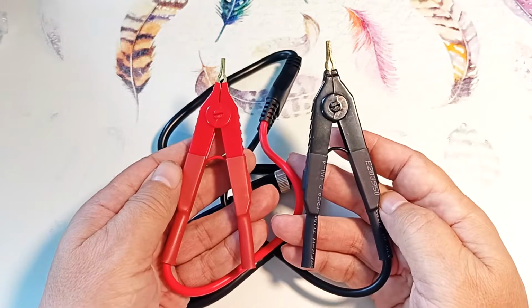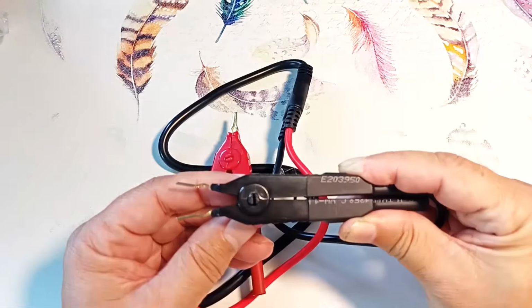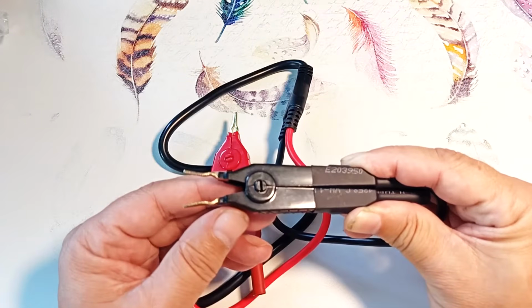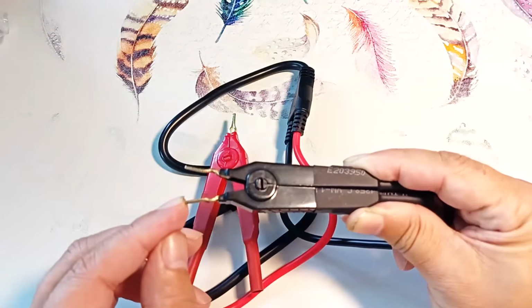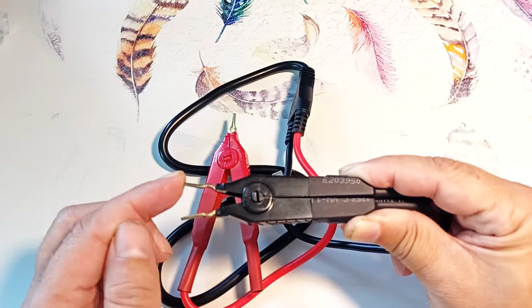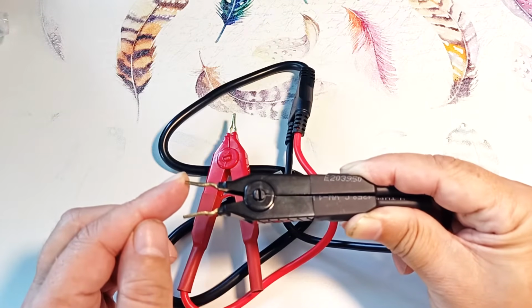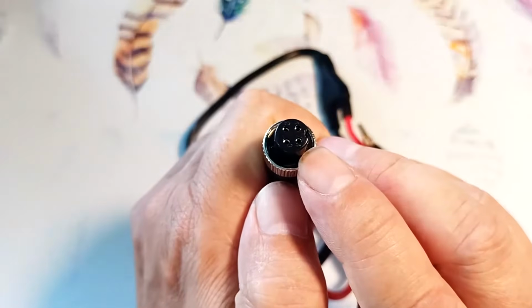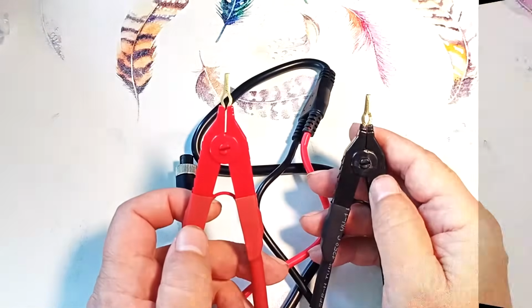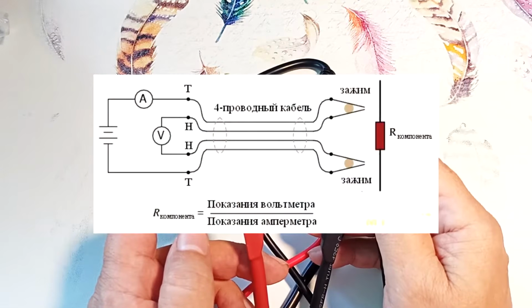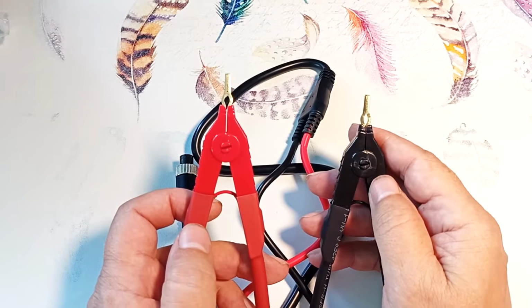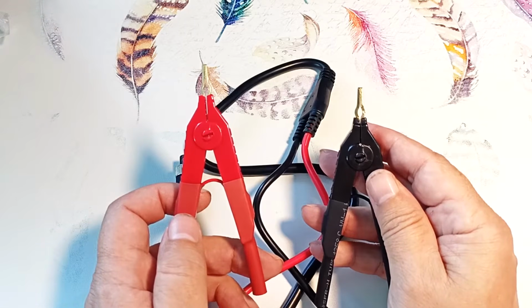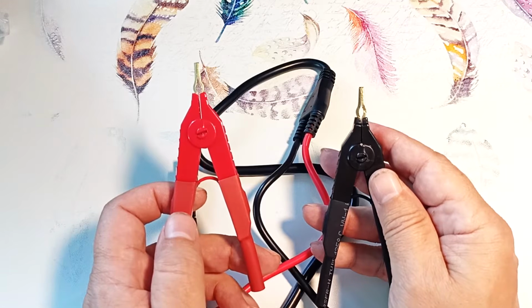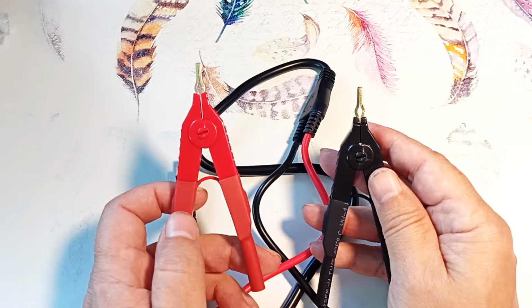Kelvin probes deserve a more detailed look - these are no ordinary crocodile clips. Each crocodile has at least 2 wires, and each wire goes to its own probe contact: one wire to this pin, the other to this pin, and these two contacts are isolated from each other. In total there are 4 wires going to the probes, connecting to 4 pins in the connector, resulting in 2 current wires and 2 voltage wires. We won't go into the physics of the process since it's complex and would take a lot of time, but the peculiarity of this 4-pin connection is that it allows measuring voltage and resistance with great accuracy. In addition, the device generates a test signal with a frequency of 1 kHz, resulting in accurate readings on the display.